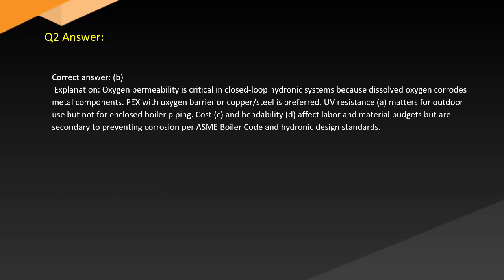Answer. Correct answer: B. Explanation. Oxygen permeability is critical in closed-loop hydronic systems because dissolved oxygen corrodes metal components. PEX with an oxygen barrier, or copper or steel, is preferred. UV resistance (A) matters for outdoor use but not for enclosed boiler piping. Cost (C) and bendability (D) affect labor and material budgets but are secondary to preventing corrosion per ASME boiler code and hydronic design standards.